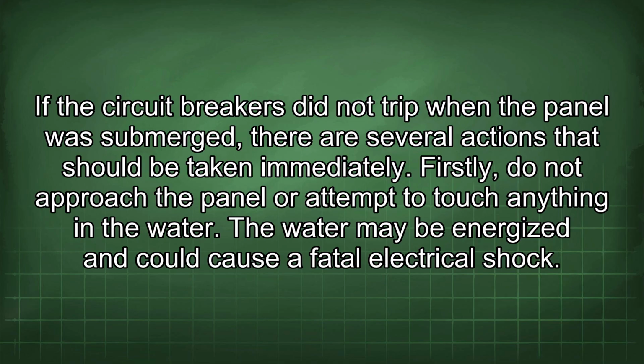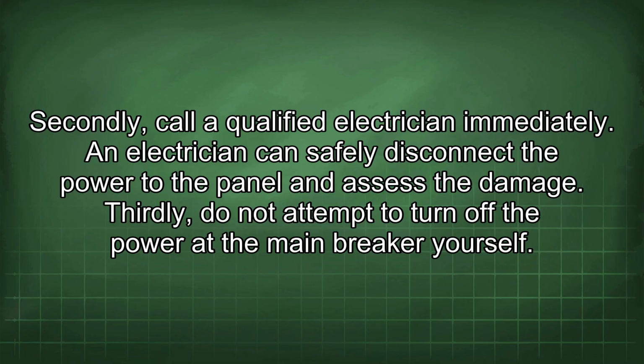If the circuit breakers did not trip when the panel was submerged, there are several actions that should be taken immediately. Firstly, do not approach the panel or attempt to touch anything in the water. The water may be energized and could cause a fatal electrical shock. Secondly, call a qualified electrician immediately. An electrician can safely disconnect the power to the panel and assess the damage.